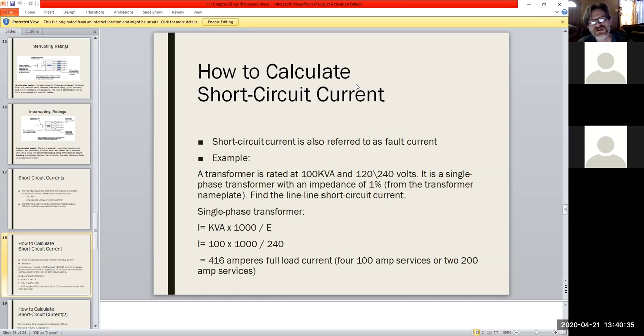So then we have to take the rating. In this case, we have 100. So 100 times 1,000 divided by 240, and they figure out the 416 amp full load current. So how would you do that? Well, in some cases it'd be 4 100 amp services where you would literally have 4 different panels, right? 1, 2, 3, 4, each one rated at 100, or 2 200 amp services. And believe it or not, some of the homes these days actually do call for a 400 amp service, in which case you would be doing a dual panel, or possibly the 4 panel, or some kind of combination thereof, you know what I mean?